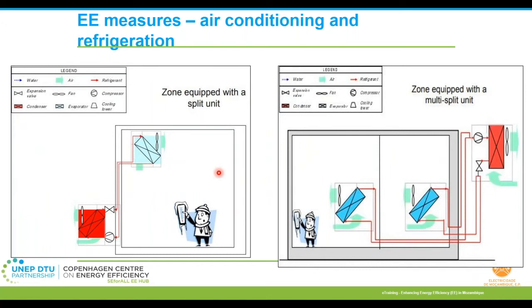Then of course, zoning. This is quite important. Often I see large office spaces with about 50 to 100 people sitting in a big large hall, and only one or two working in that. For that, the entire office space has to be conditioned, and the air conditioning systems have to be switched on. So instead of that, if you have zoning systems in place, like instead of one zone you have multiple zones, then you can actually cater to individual zone needs. That way you will not be requiring to use larger systems. You can always optimize your consumption levels.